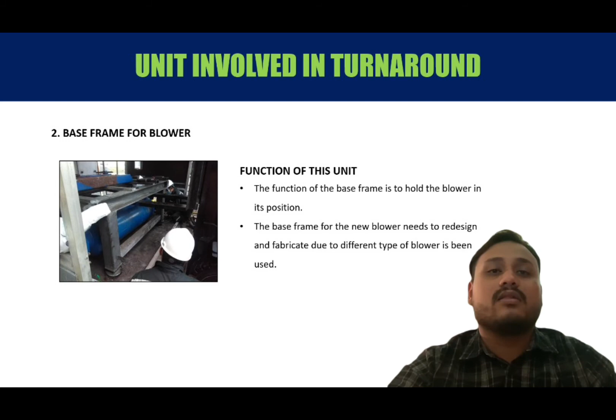Due to high vibration caused by blower rotation, the base frame needs to be designed according to the blower specification and size. It is to ensure the blower is securely held in its position. The base frame for the new blower needs to be redesigned and fabricated because a different type of blower is being used. The blower base design is different, so modification of the old base frame is prohibited, and this is to ensure the vibration on the new blower can be reduced to the optimal scale. Then we will talk about the maintenance task for this unit.